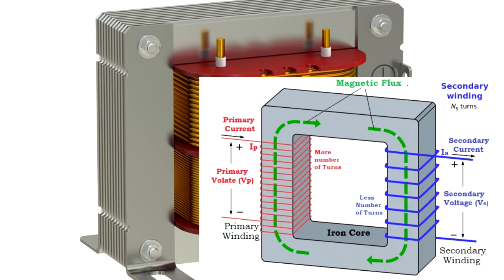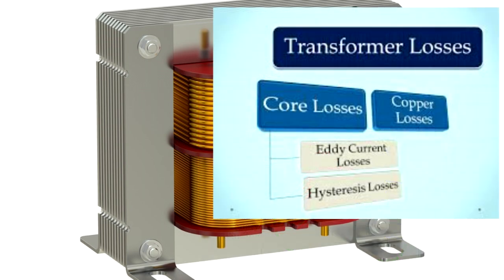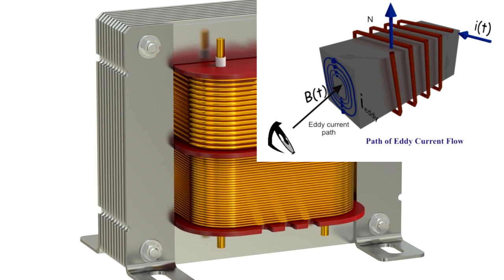So it is the magnetic properties of the transformer's core material which result in these losses, and they could be due to the type of magnetic material that's used or the construction of the transformer. And our core losses can be further subdivided into two different categories, and they're called hysteresis loss and eddy current loss. So let's take our eddy current losses first.